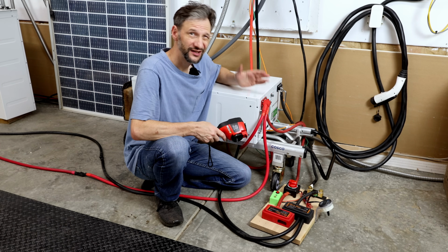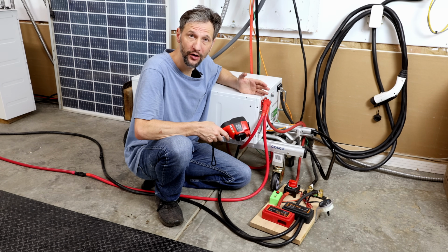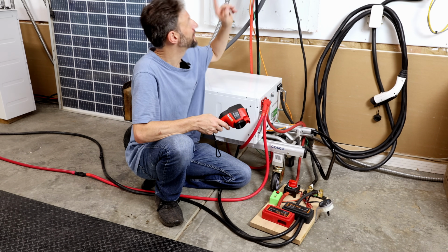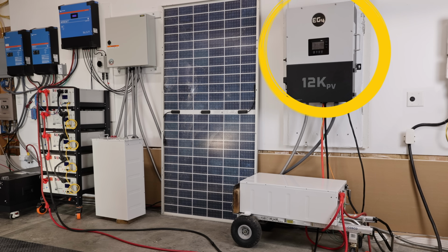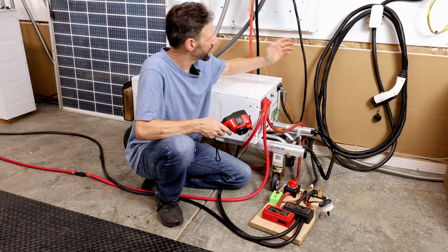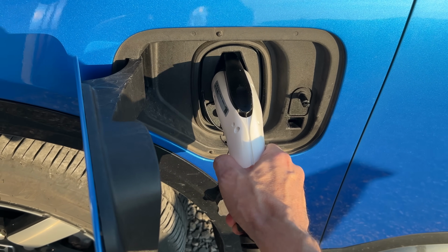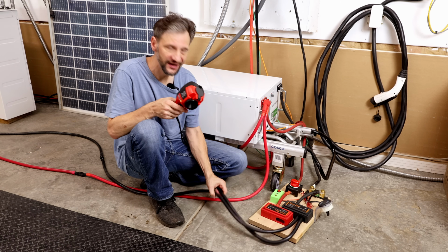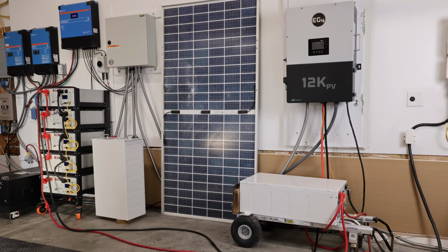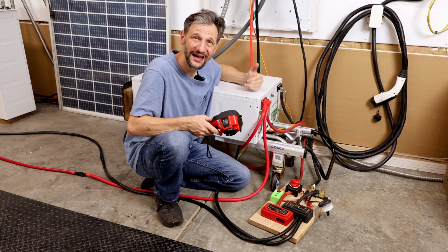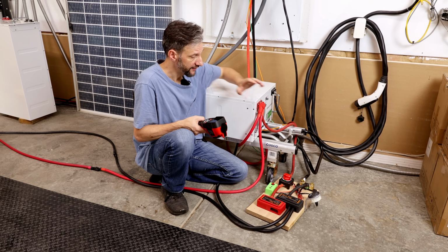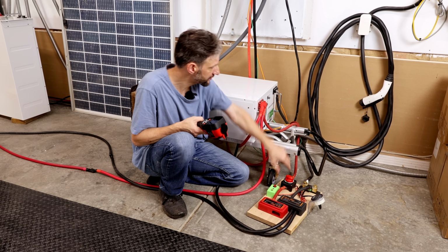All right, I want to push this thing to its maximum 200 amp output, or 10,000 watts, and my EG4 12K PV can only pull 8,000 watts. I'll connect my EV, that'll pull 8,000 watts, and then I've run an extra set of cables here over to my Victron system, and I'll pull another 2,000 watts plus out of that, so we can get a full 10,000 watts out of this. To measure that, I've connected both inverters through my Victron shunt to this battery.